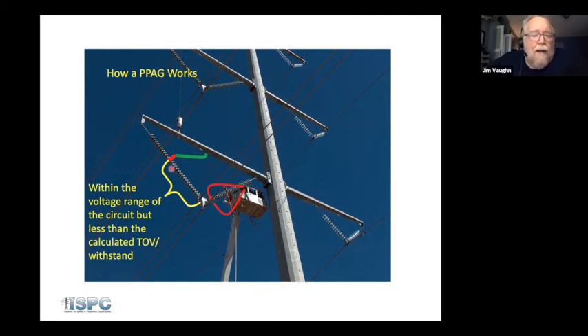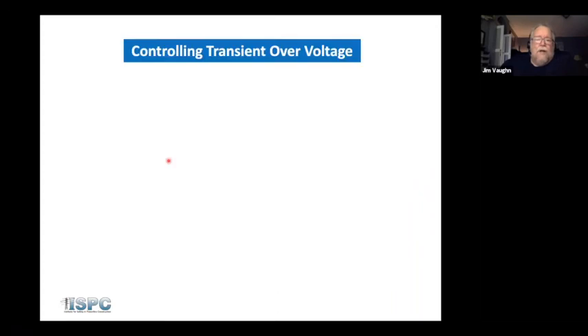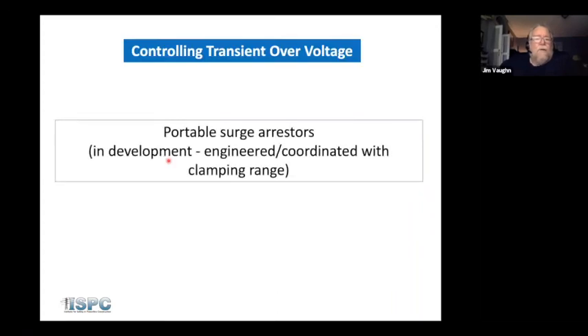that's a span away. So the problem with a PPAG is that it can cause an inadvertent lockout, but it's going to be totally resistive, and it's unlikely to actually create a TOV if it does trip the circuit, but it's obvious that it could occur. So we are also in development; engineering companies are working on developing portable surge arresters, which would be preferable to a PPAG. So what we would do is go a structure away on either side of our work location, and we would install portable arresters on the circuit to reduce that.